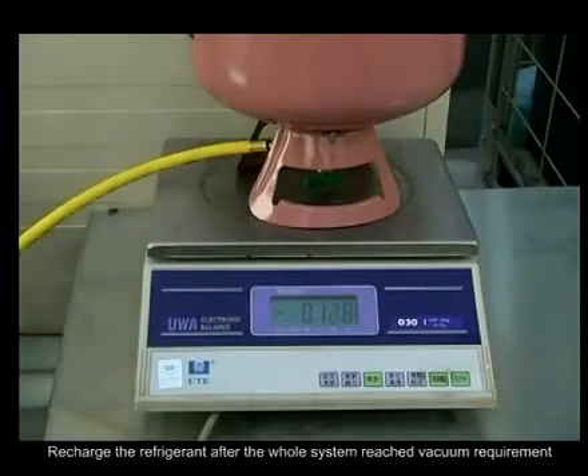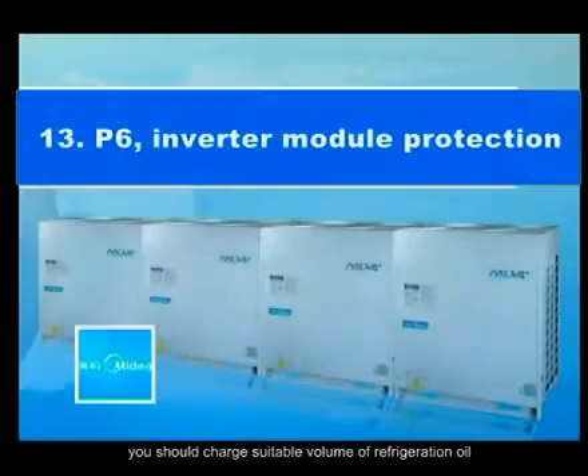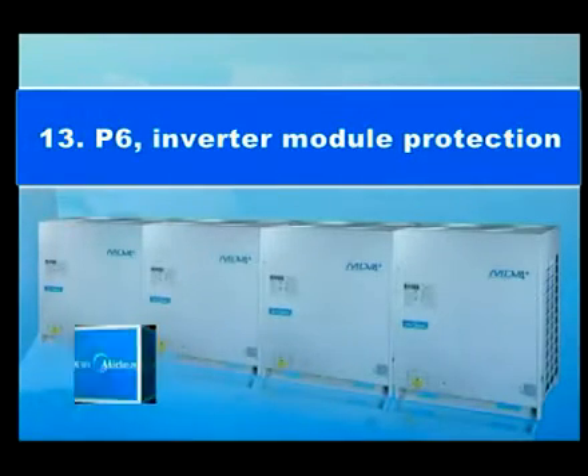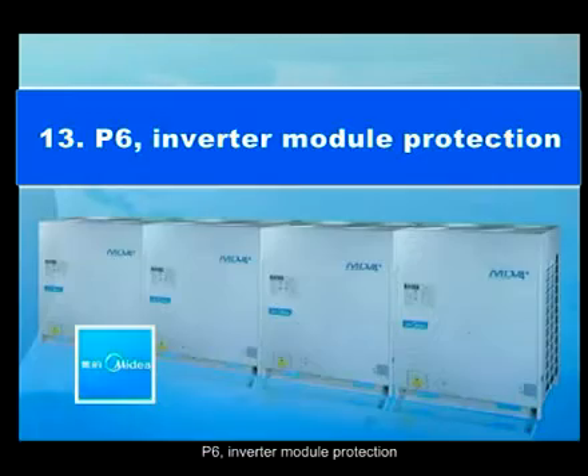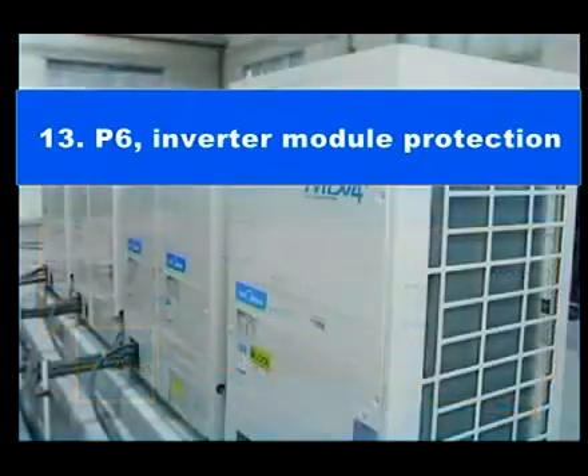Recharge the refrigerant after the whole system reaches the vacuum requirement. During the process, if refrigeration oil goes out, you should charge a suitable volume of refrigeration oil. P6. Inverter module protection.